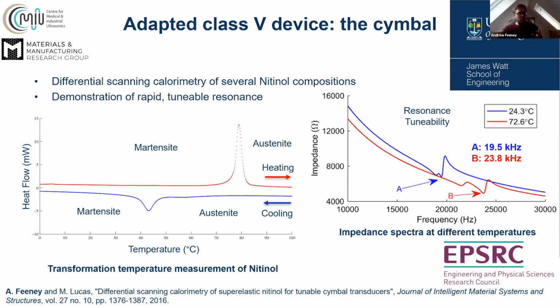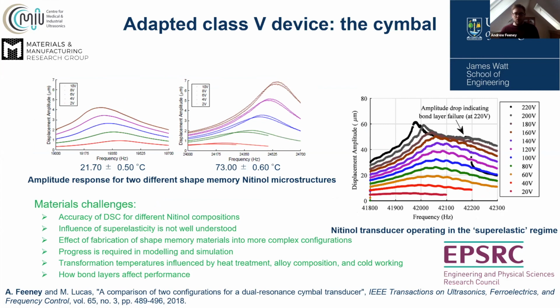Devices in general don't have to be constructed using 2 caps. I could use one, and I have done in the kind of orthopedic device concept. So shown here as well are amplitude responses that I measured for both end caps, both caps on the transducer. Now, in the superelastic regime, on the right-hand side, I actually see ripples in the responses, and there's clearly something happening at the microstructural level that I need to study further. But it was a really interesting result. The transducer was operational, but we just see these ripples that I didn't see when I was looking at a different composition of nitinol, which is on the left.